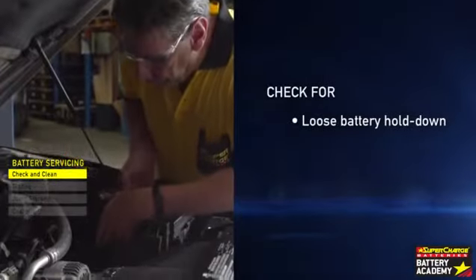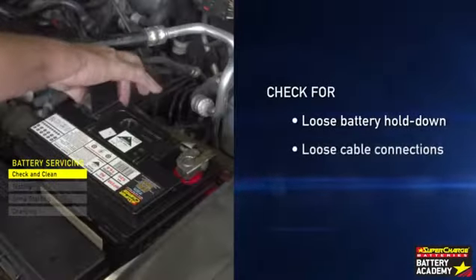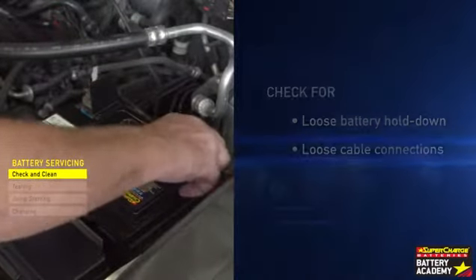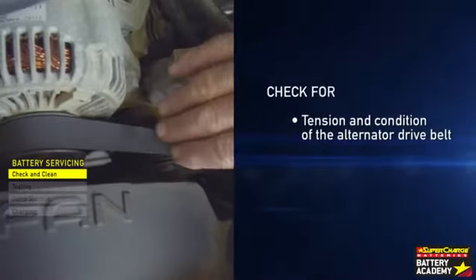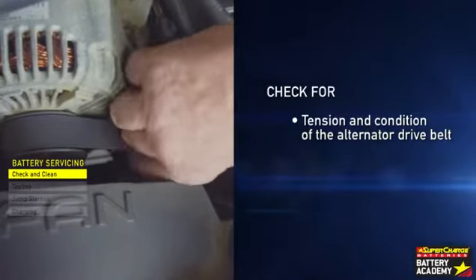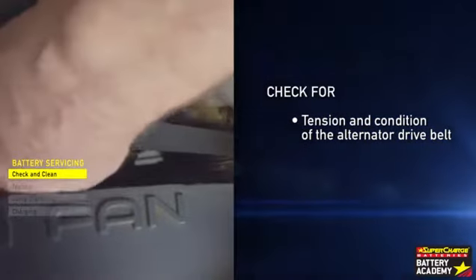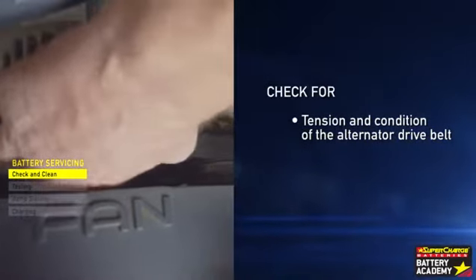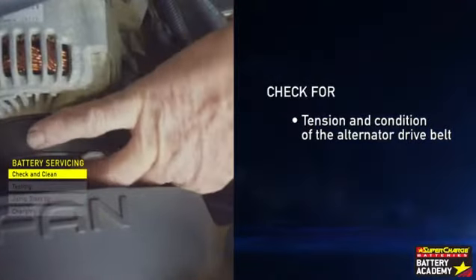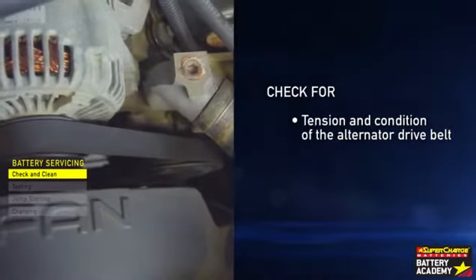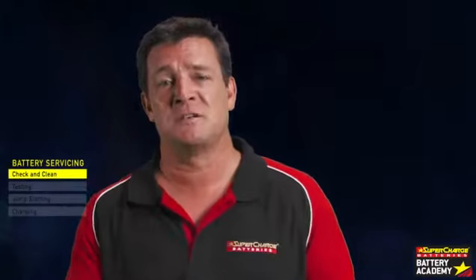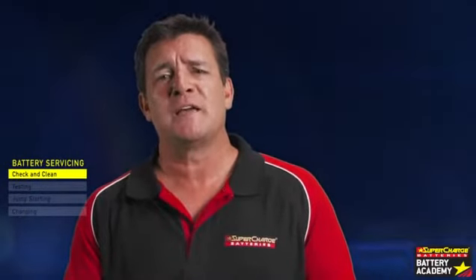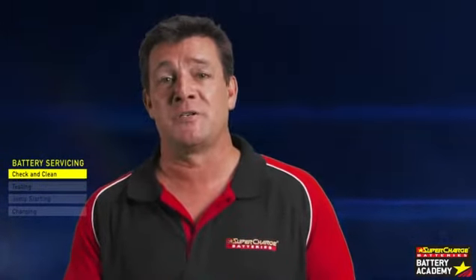Check for a loose battery hold down and loose cable connections. Tighten as needed. Check the tension and condition of the alternator drive belt. A loose belt will prevent proper charging and must be tightened. A belt that is too tight will reduce alternator life. It should be loosened to manufacturer's specs. A frayed or glazed belt will fail during operation.